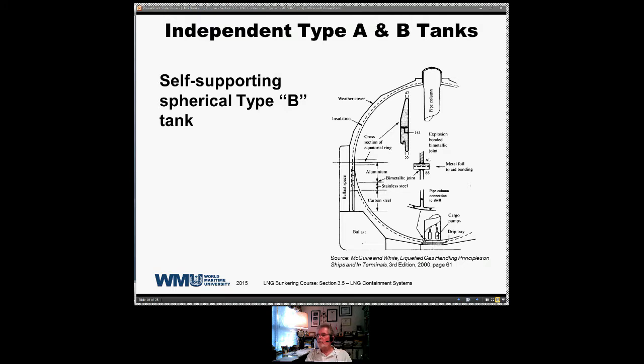And if one were to climb down inside the hold space of this ship, you could actually come down here and walk underneath the tank and around it. This type of configuration is not as volumetrically efficient because you have a lot of wasted space. The hold, though, can be kept in an inert environment, which is very advantageous and safe. The secondary barrier in this type of tank is a little drip tray that sits underneath the tank. The theory behind a round tank is that a sphere is always going to leak before it fails, if this ever does happen. And if you do get a leak of liquid inside the tank, that liquid is going to hug the surface of the tank until it gets down to the bottom. And if there's any liquid left over, it will actually drip into this drip tray in the bottom, which protects the hull.